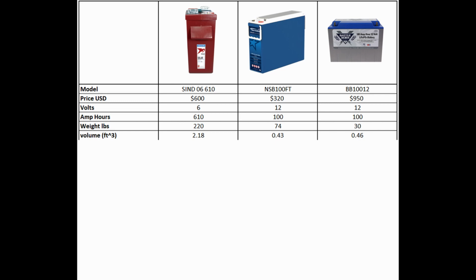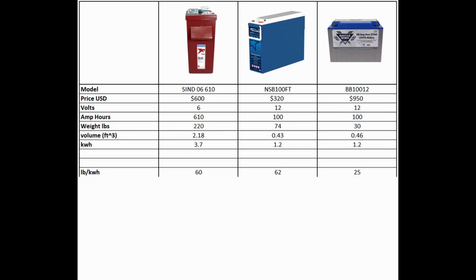With those specs out of the way, let's start with some quantitative metrics. First, the specific energy, or in this case pounds per kilowatt hour, to keep the numbers easy to compare. So for the flooded lead acid battery, we have 60 pounds per kilowatt hour. Here a smaller number is better. In the AGM battery, we have 62 pounds per kilowatt hour. And in the lithium battery, we have 25 pounds per kilowatt hour. Much better than the lead acid batteries. Here we can see that both lead acid technologies are similar and that lithium is about 2.5 times as energy dense. Next, energy density, or in this case, cubic feet per kilowatt hour.